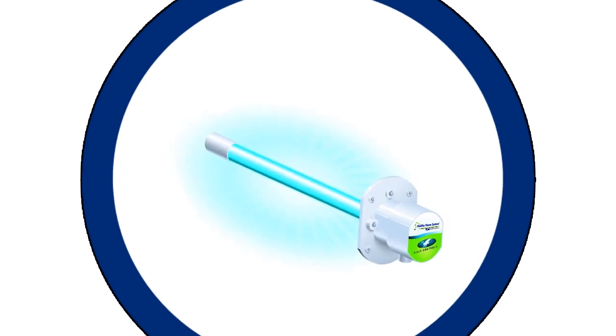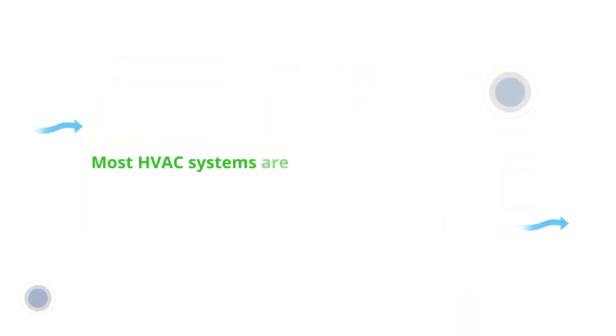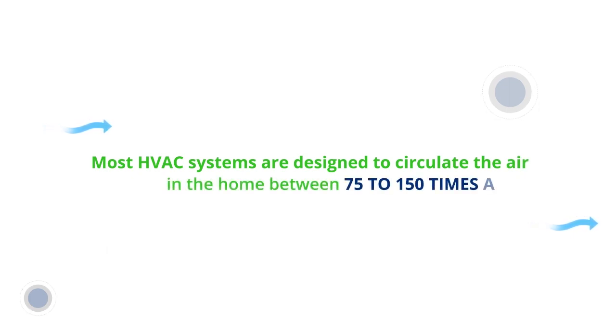A UV lamp mounted in the HVAC duct system can be effective in controlling bacteria and germs in indoor air. The UV lamp neutralizes the germ molecule's DNA and makes them unable to replicate. As indoor air circulates through the duct system, it's consistently bathed in UV light. Based on the design of central air systems, each molecule of air will circulate through or pass over the lamp 75 to 150 times a day.